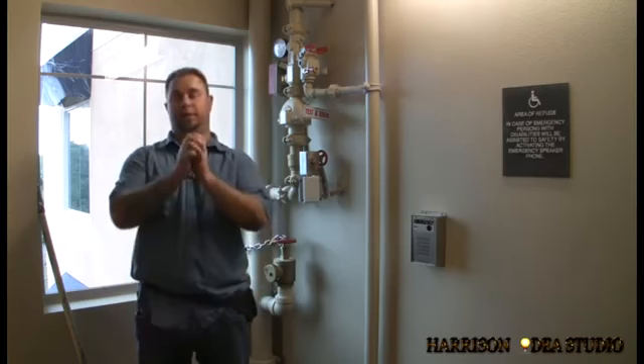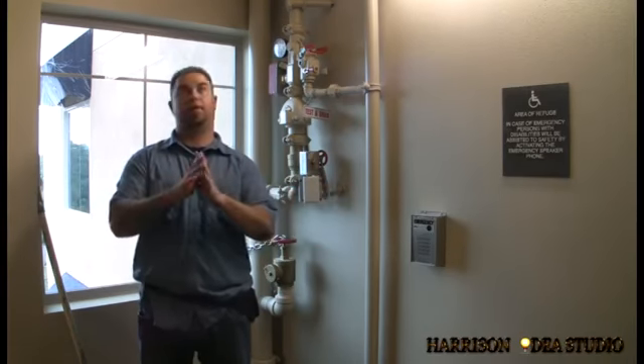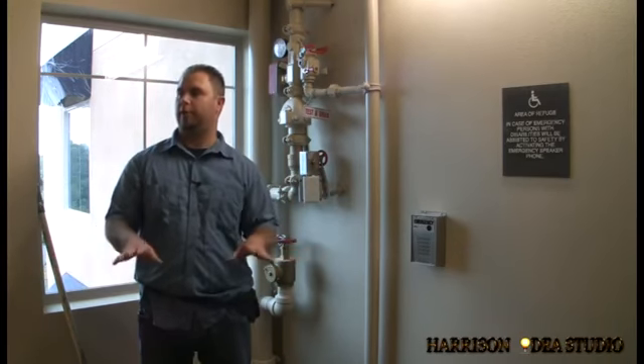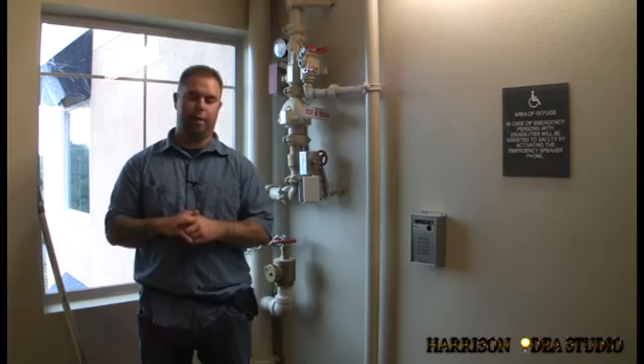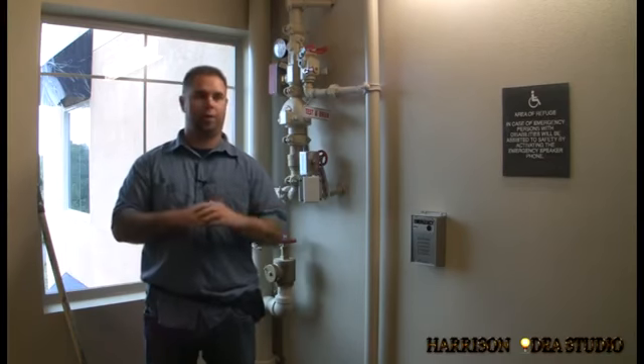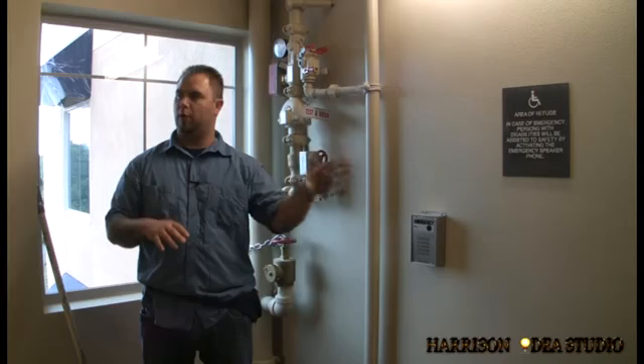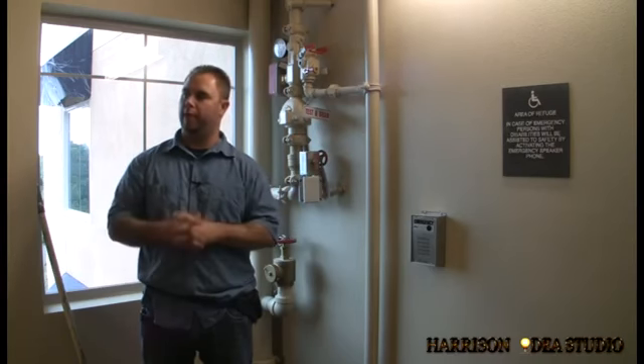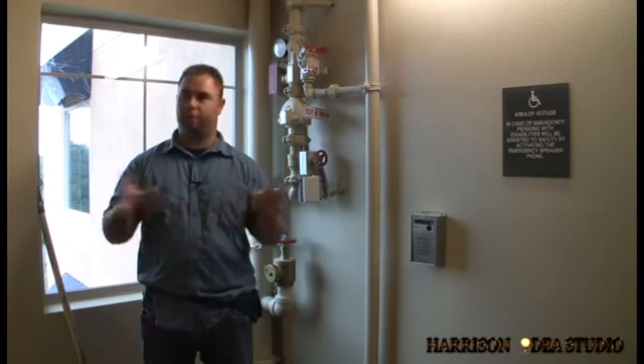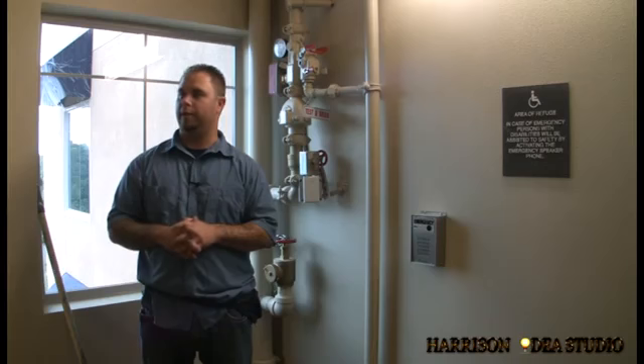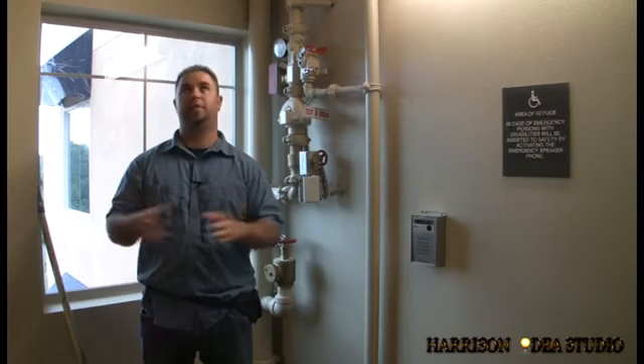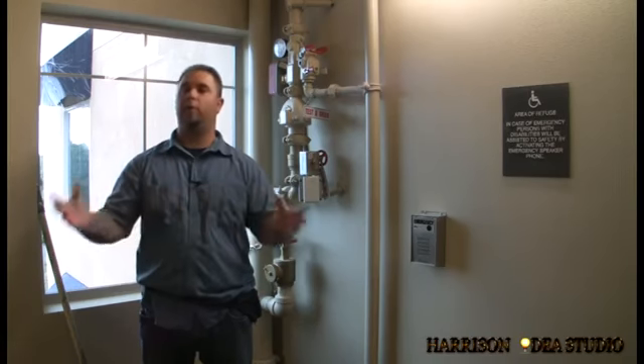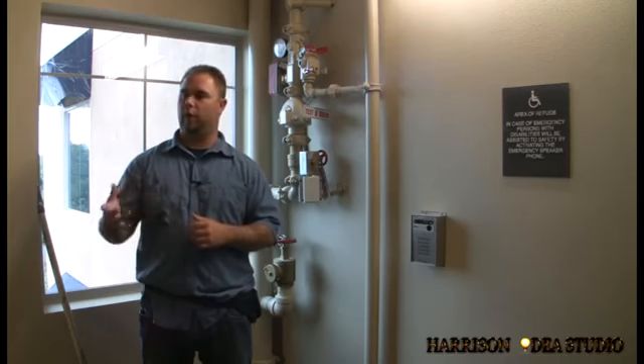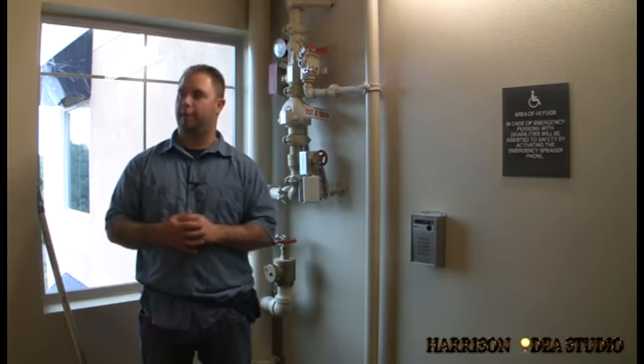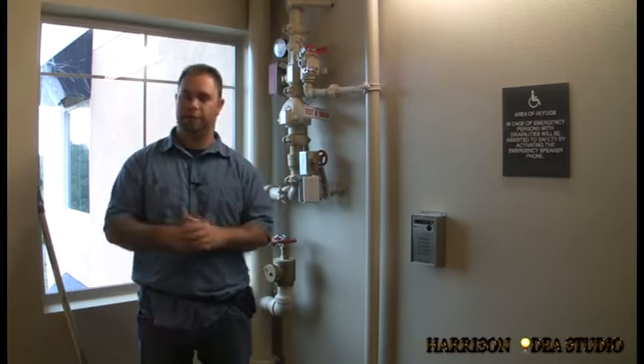What happened is somebody by mistake breaks that thing. What happens? It's going to discharge water. 13 gallons a minute will come out of that sprinkler. And the fire alarm will go off. All your horn strobes will go off, your exterior bell will ring. Everybody's probably going to panic and evacuate, but as long as management or maintenance figures it out, and the fire department will come out. They'll get a phone call from the monitoring company. The fire department will show up automatically just because it's monitored that way.